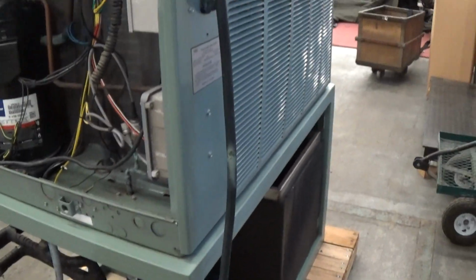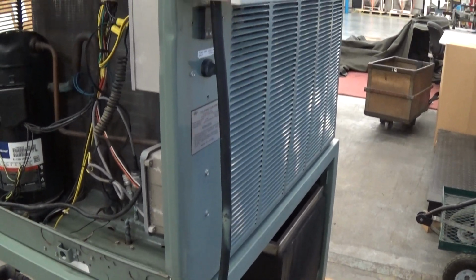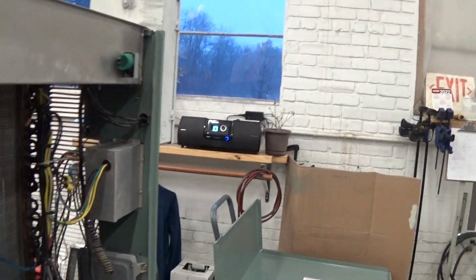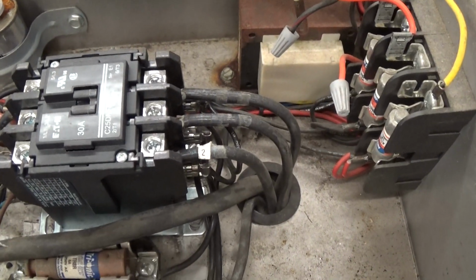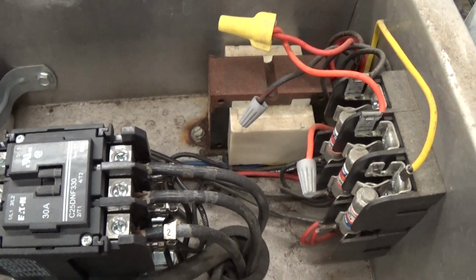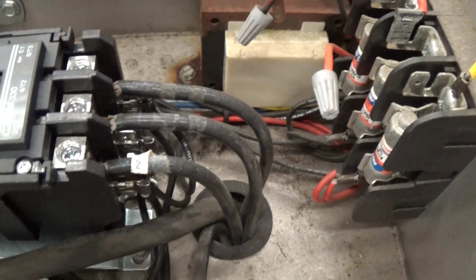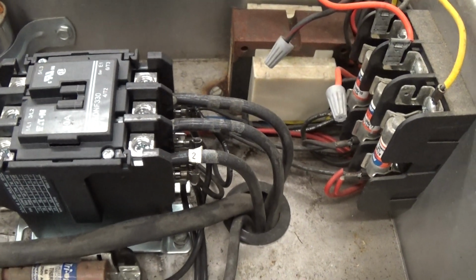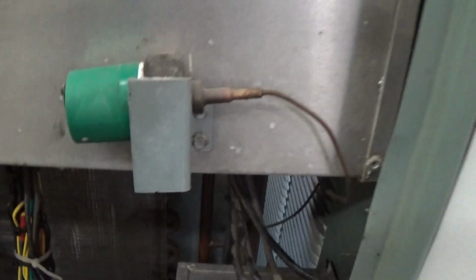Related to power, it's 3-phase 230 volt. It can handle as low as 208, as high as 240. Again, we're going to ship it with this disconnect here. We may remove the disconnect and put it in a box. But anyway, the main power connection comes right up here. You can see these lines coming from the disconnect, and comes right to that main primary contactor that you see right here. L1, L2, L3, and then your ground right here. So if you get the phase wrong at initial startup, you want to swap any 2 of those. Again, this is geared towards the electrician who will perform your initial connections.